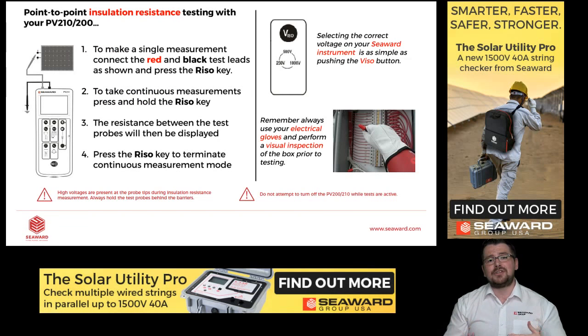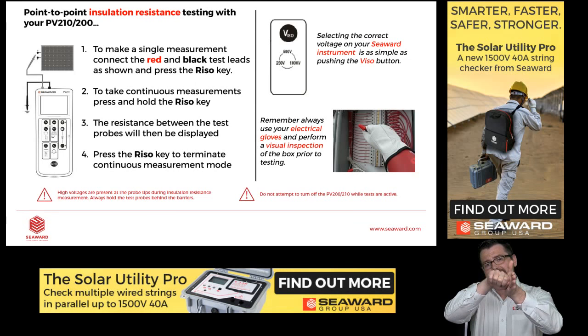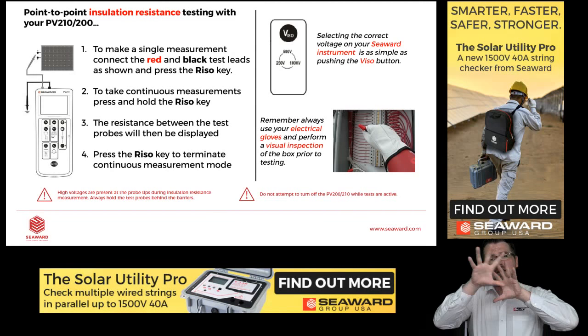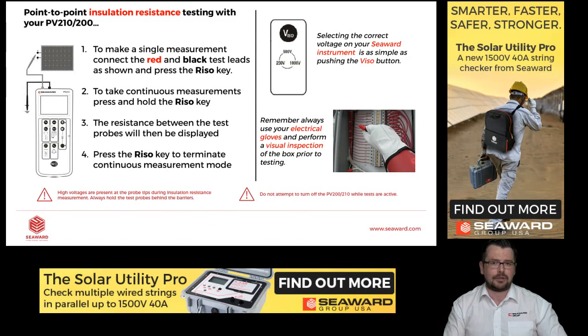So again, very similar to the RPE method I described earlier, with the PV210 and the PV200, you can do a separate megger test, as they call it here in America, up to 1 kV, and we connect to the ground. We can do into the positive, into the negative, we can do the frame, and we're just making sure that the insulation resistance throughout the array is consistent and at a good level. The PV210 can also do this as part of an auto sequence where it will give a curve trace, insulation resistance at the same time, which is really useful if you're looking to save time on site.